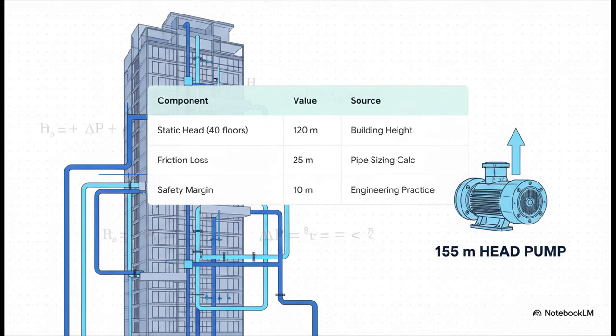And this is the part that changes everything. Look at this example for our first 40-floor zone. The static head is only 120 meters. You add in friction and a safety margin, and suddenly we only need a pump that can provide 155 meters of head. That's a powerful pump for sure, but it's a standard, readily available piece of equipment. We've taken an impossible problem and made it totally manageable.